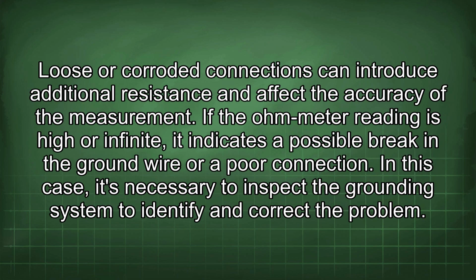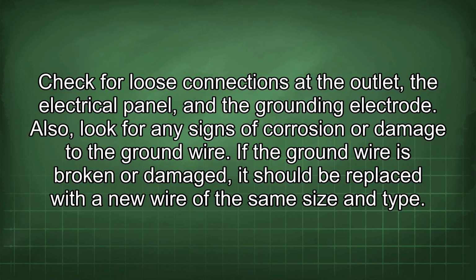Loose or corroded connections can introduce additional resistance and affect the accuracy of the measurement. If the Ohm-Meter reading is high or infinite, it indicates a possible break in the ground wire or a poor connection. In this case, it's necessary to inspect the grounding system to identify and correct the problem. Check for loose connections at the outlet, the electrical panel, and the grounding electrode.